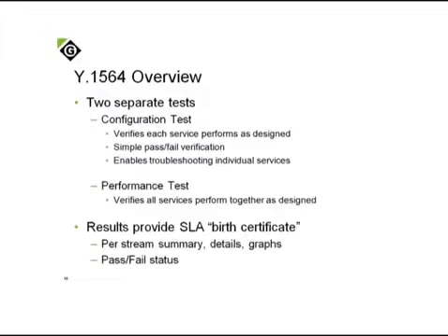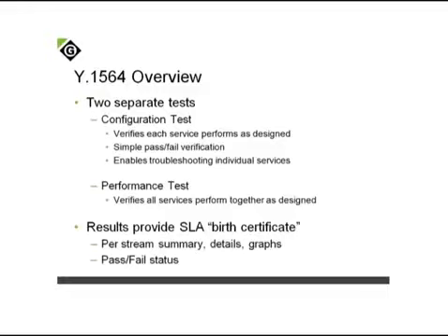Then once it tests each service, and those service tests can be as low as 5 seconds up to 5 minutes if you want. After that, your performance test is going to verify all the services and make sure that they perform as designed as well. So the performance test can run as low as 5 minutes, and it can run all the way up to 15 minutes, 24 hours if you want to, or longer.